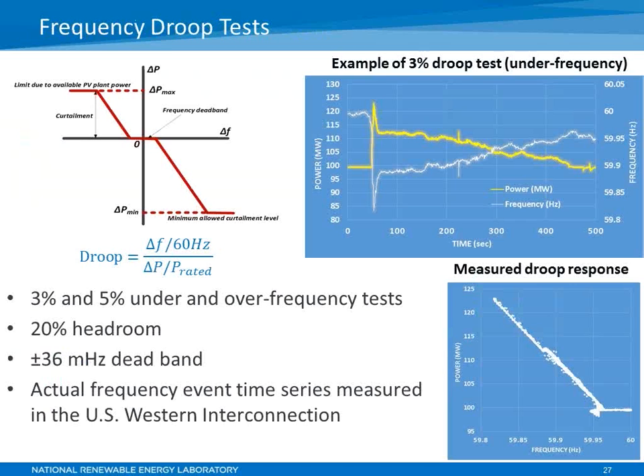The next type of test we did was to demonstrate the ability of a PV plant to participate in primary frequency response. The ability of a power system to maintain its electrical frequency within a safe range is crucial for stability and reliability. Frequency response is a measure of an interconnection's ability to stabilize the frequency immediately following the sudden loss of generation or load. The sudden loss of generation or load manifests itself in a large frequency excursion. Due to the limited amount of project time we had with this plant, we couldn't have the luxury to wait until this event happened naturally. So again, we just provided historically measured frequency event data measured in a U.S.